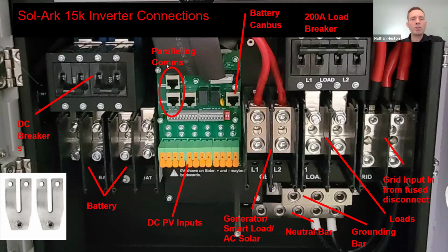The paralleling communications: if you're going to parallel a couple of Sol-Arks, these 2 ports in the center of your screen are used for paralleling, and you'll just daisy chain these. So if you have 3 inverters, inverter 1 to inverter 2, inverter 2 to inverter 3, back to inverter 1. So neither of these ports would ever be open if you have parallel communications. I'll talk about the DIN rail connections here, and the connections for things like AGS, etc., in a minute. But before I get into these dip switches, let's talk about the CAN bus connection. If you're using our communicating batteries, this is where that home run from the battery bank to the inverter would be. And this is the communications port where the battery and the inverter communicate to each other.